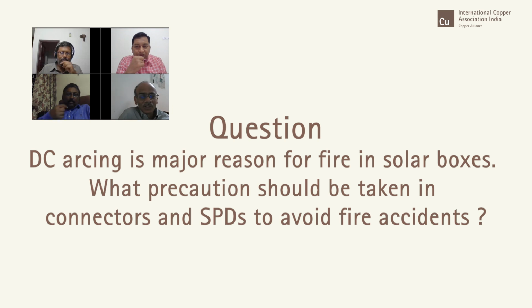I have already listed what the causes are and what needs to be done. The important thing is, of course, many times they give the torque, what torque you have to apply. If you exceed that, the terminal itself can break. So you have to ensure that you make the connection properly. And many times you have locking arrangements available, which ensure that. And you have spring washers, which is of course for mechanical systems, but there are many ways of ensuring that you have proper contacts made.